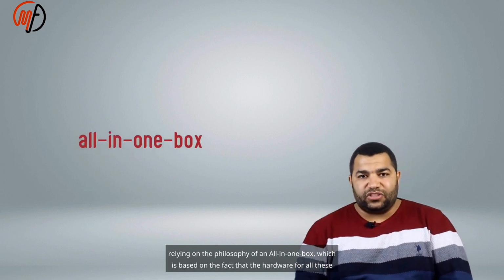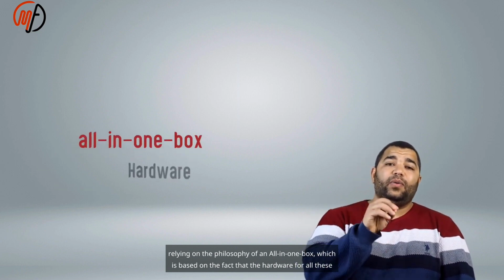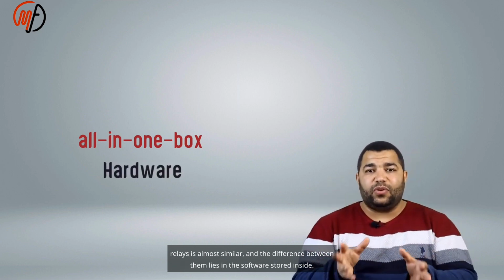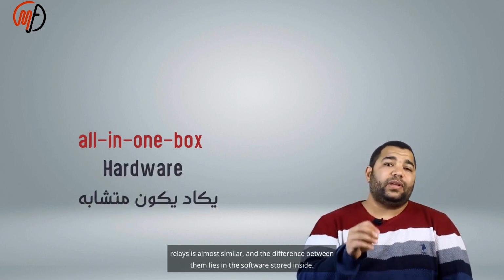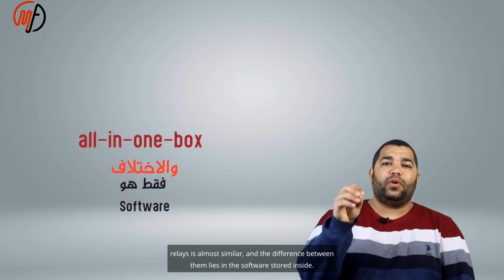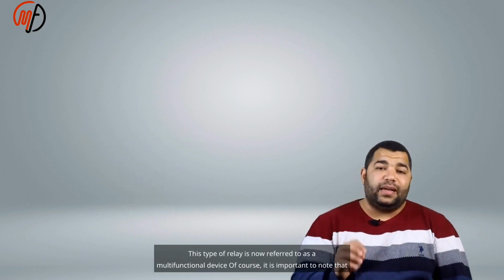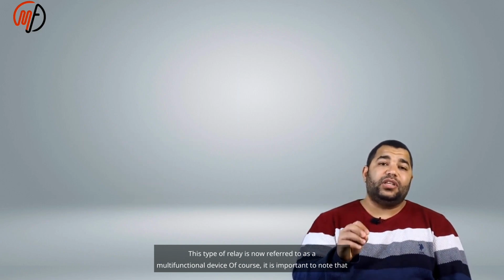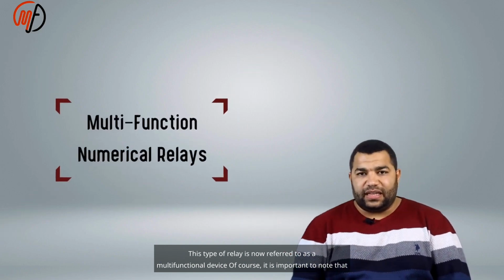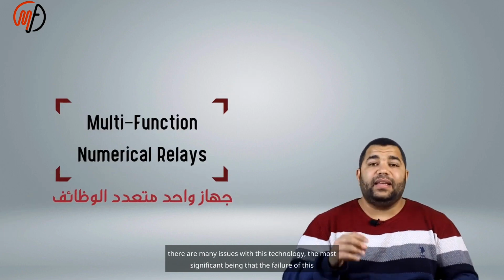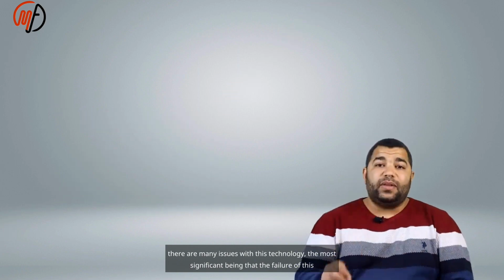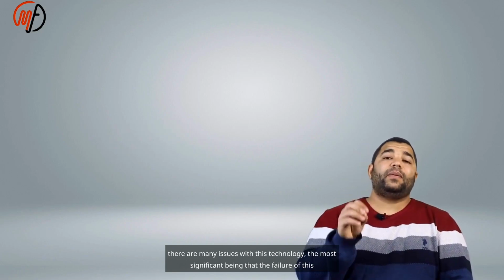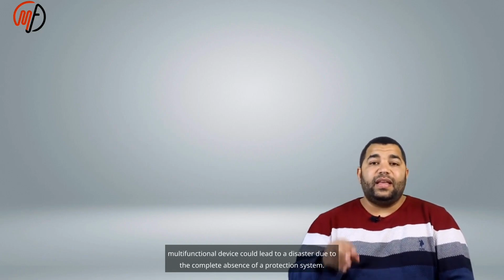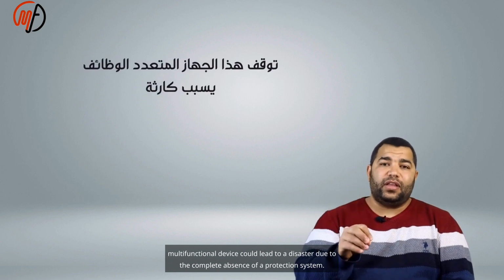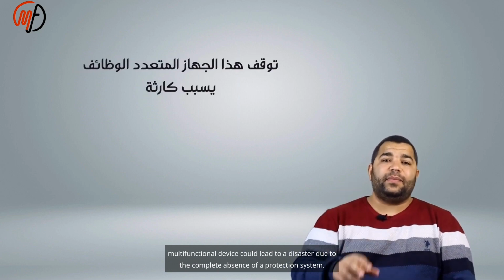After this development, the producing companies began to integrate many protective devices into one unit, relying on the philosophy of an all-in-one box, which is based on the fact that the hardware for all these relays is almost similar, and the difference between them lies in the software stored inside. This type of relay is now referred to as a multifunctional device. Of course, it is important to note that there are many issues with this technology, the most significant being that the failure of this multifunctional device could lead to a disaster due to the complete absence of a protection system.